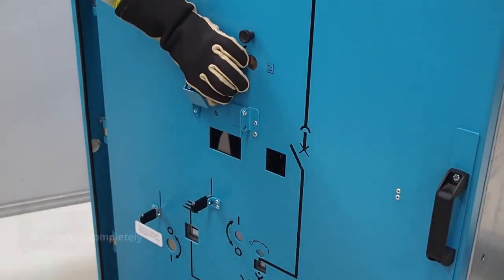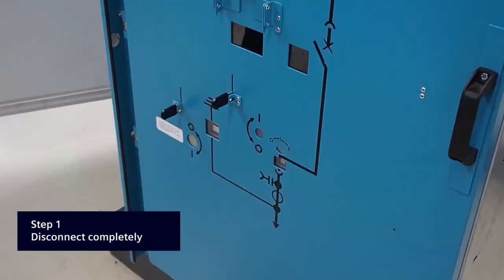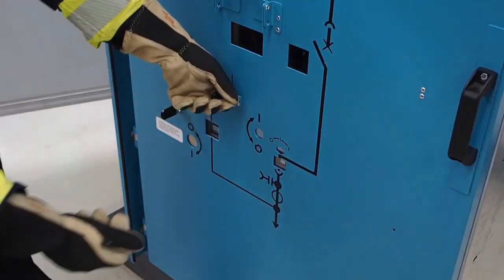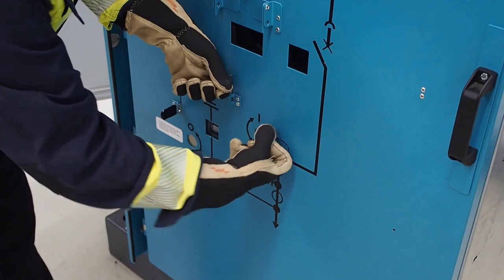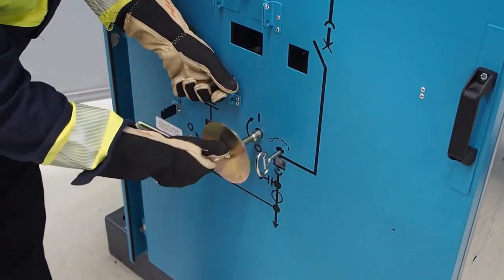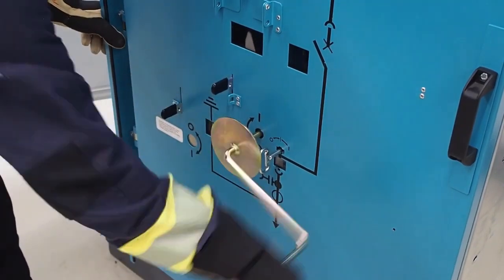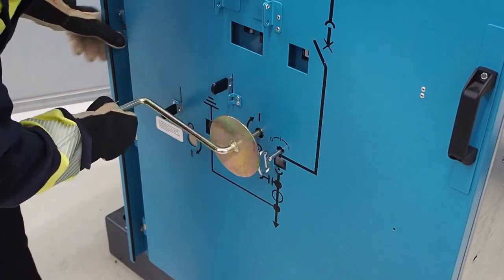The first step is to switch off the circuit breaker and make sure that the incoming feeder for energizing the bus bar is switched off. Then withdraw the circuit breaker from its panel and place it in the test position.